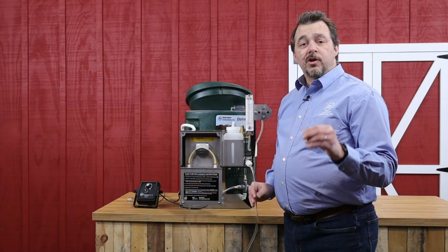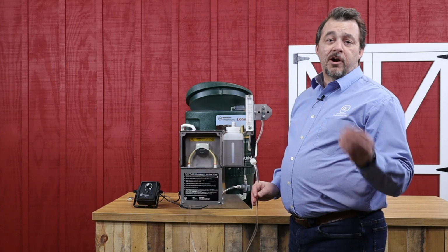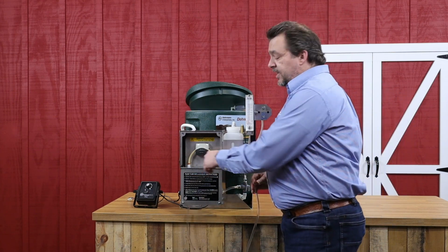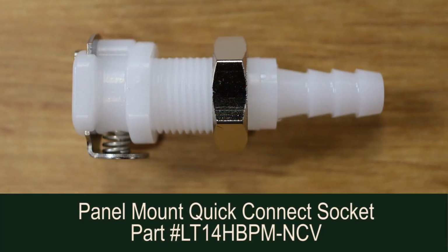The part number is in the bottom of the video here, so you can take a look at that. For units that have been produced prior to 2019, these fittings actually had a check valve in them. And if the systems were not flushed out often enough, those check valves had a tendency to plug up. So those check valves can either be removed, and we have a video for that as well. A link to that video will be in the description at the bottom of this video. Or if you choose, you can replace them with a new part that does not have the check valve in it, and that part number is currently at the bottom of this video.